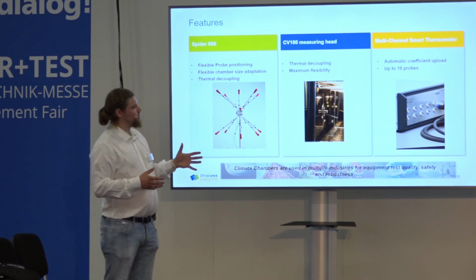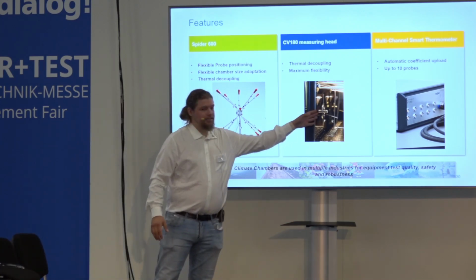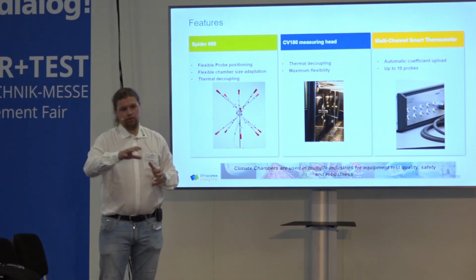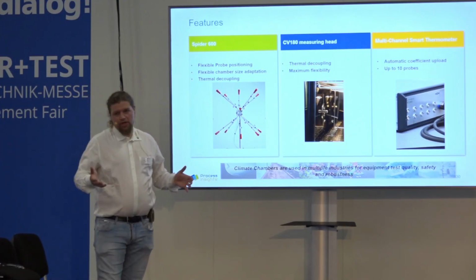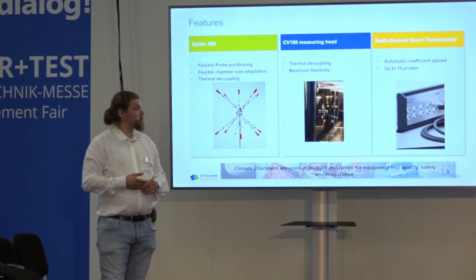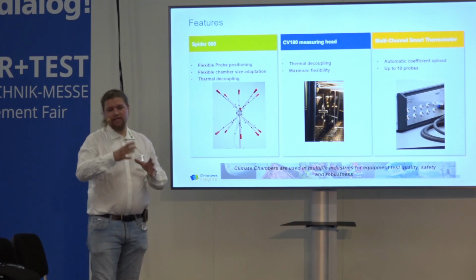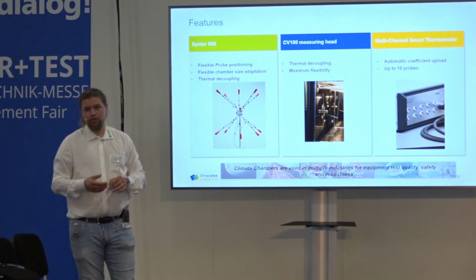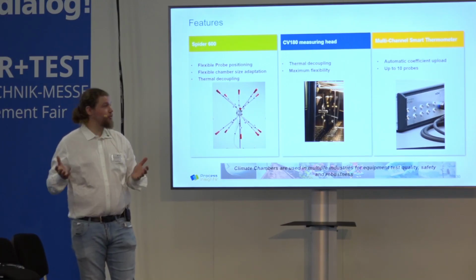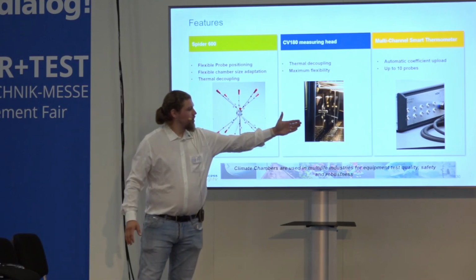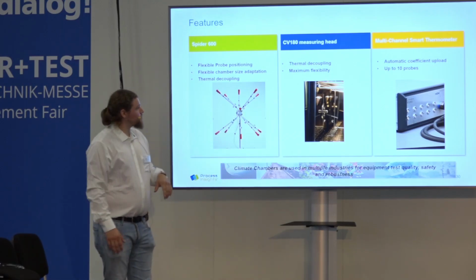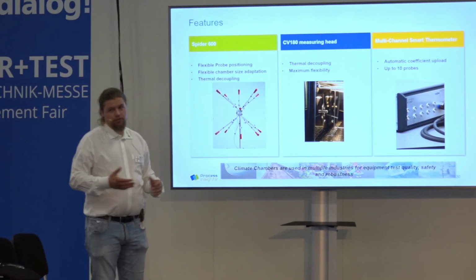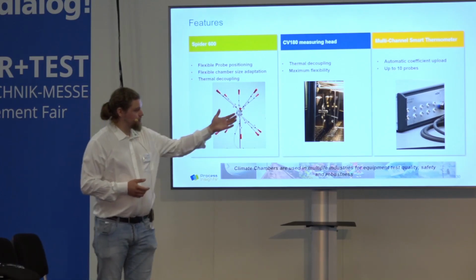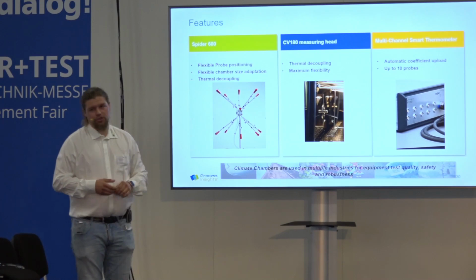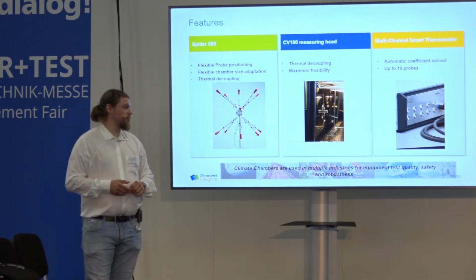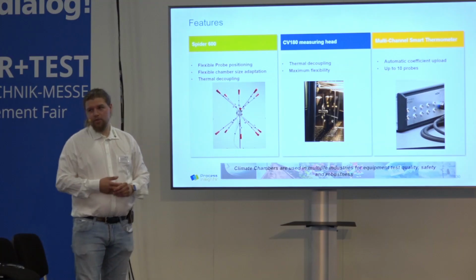So we have maximum flexibility on where we take the probe. As you can see, there is a connector where you can add a tube. So for instance, when you do electronic testing, you have a big test, but at a specific point you want to know the humidity content, as this is a significant part of your technology. Then you can also get the probe from this location. So you are maximally flexible and you have the thermal decoupling. And as already told, the temperature measurement will also be directly possible with the unit, which makes it easier for the user.